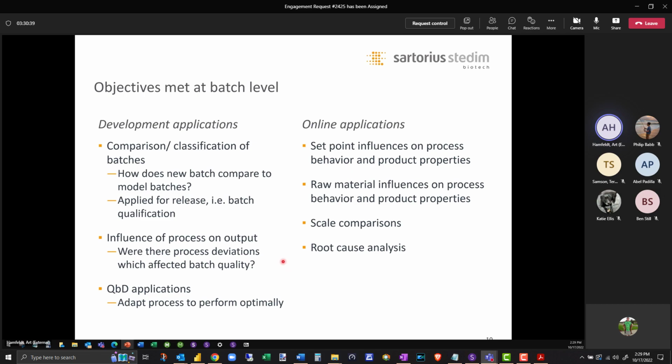So at the end of the day, you want to make sure you're only really paying attention to what's in the tank. So sometimes I'll build a model just on what's in the tank, and then I'll build a model with all the other support information. And you'd be pleasantly surprised. They very, very rarely overlap, because the support equipment is changing to keep the conditions. And so, sometimes outside equipment working harder, working less hard, sunny days, non-sunny days. Sometimes the support equipment isn't capable of reaching a certain point on a hot day. Like I have to keep this room air conditioned at 73 degrees while it's 100 degrees outside, 100% humidity.